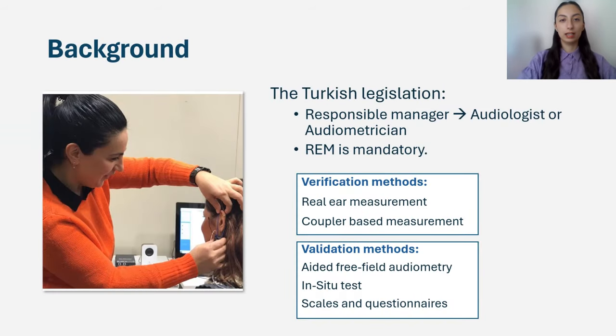In Turkey, hearing aids are provided through specialized hearing aid sales and application centers. According to Turkish legislation, the responsible manager in these centers must be an audiologist or an audiometrician. Among the verification methods used are real ear measurement and coupler-based measurements. In Turkey, the use of real ear measurement is mandatory in centers that provide hearing aids to children up to the age of 7.